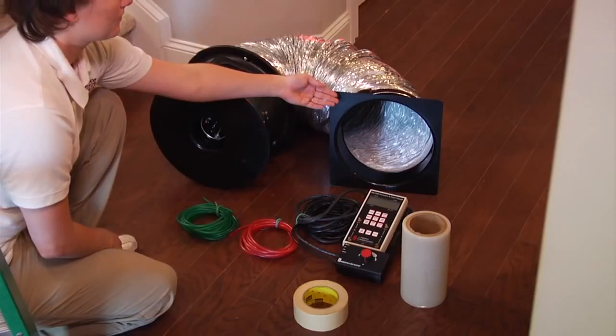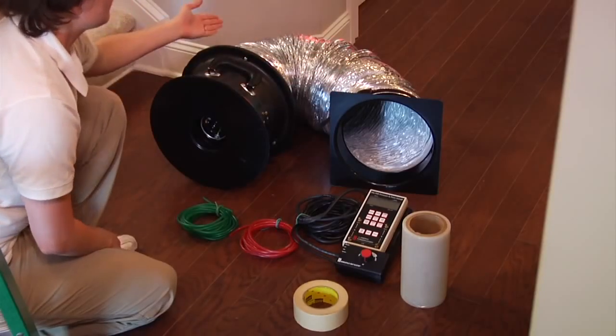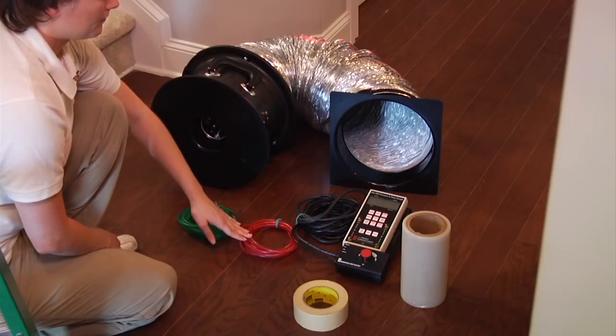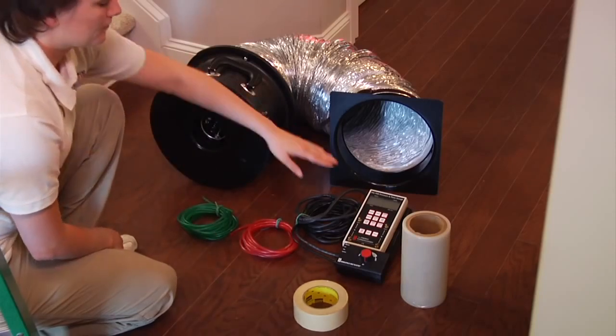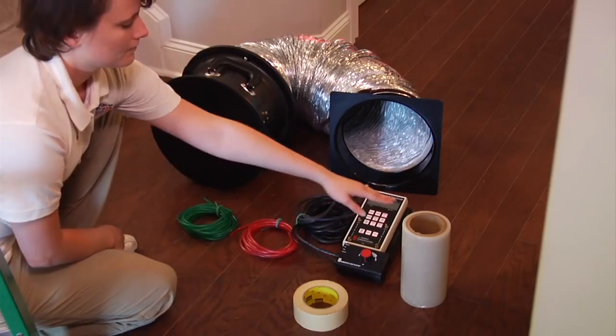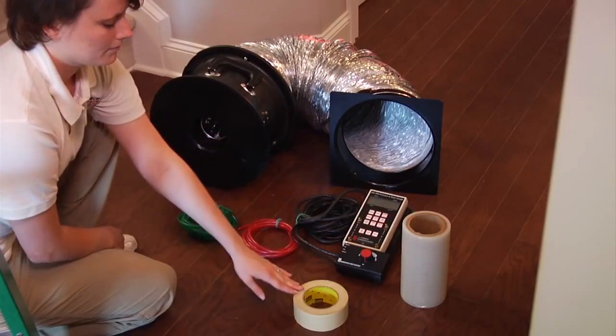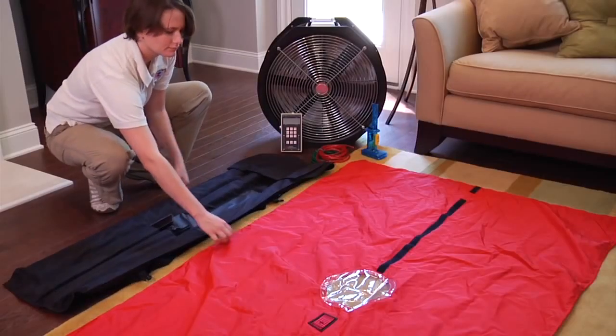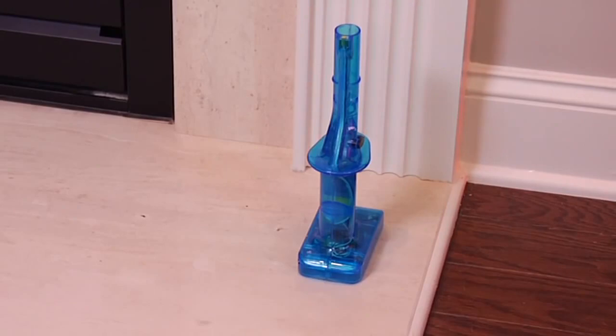Let's go over the equipment we will need and run through a checklist to make sure we have everything. You will need the following: a grill adapter, flexible transition duct, tubes, fan, and gauge. You will also need duct mask and masking tape. Finally, you will need all of the blower door equipment and a smoke stick to help find duct leaks.